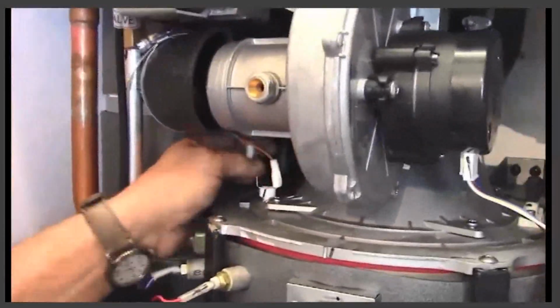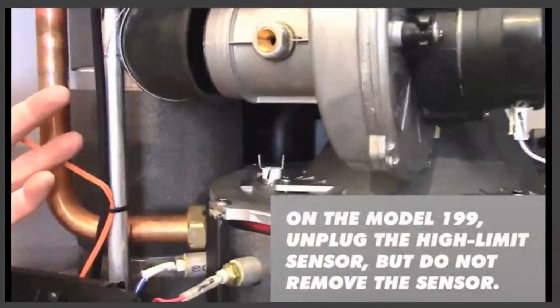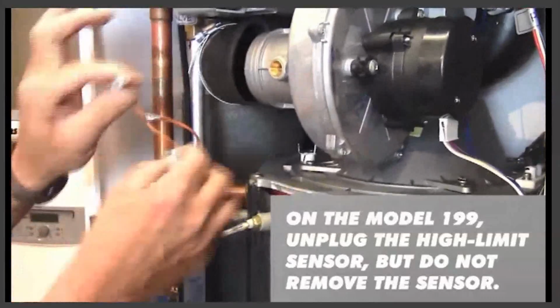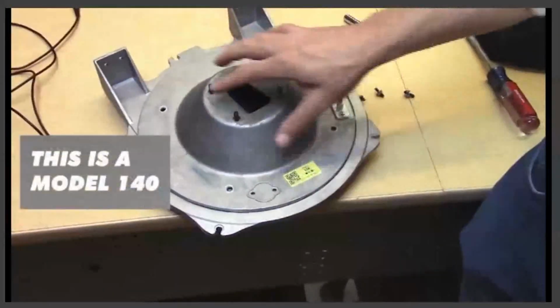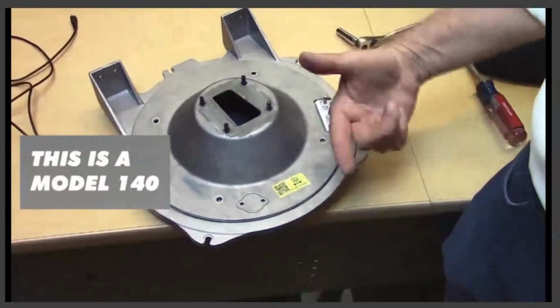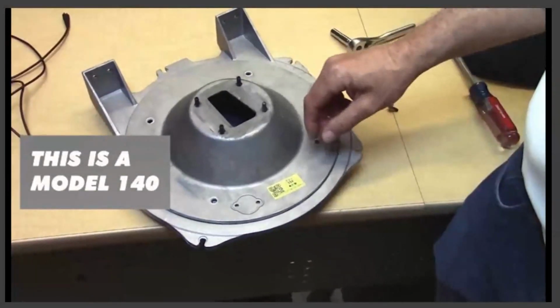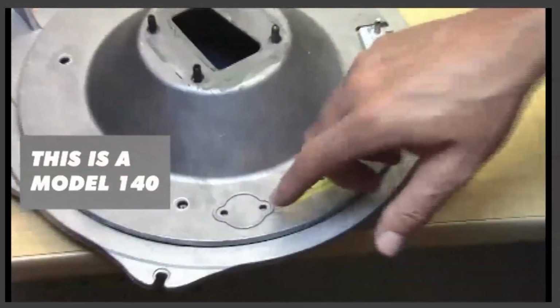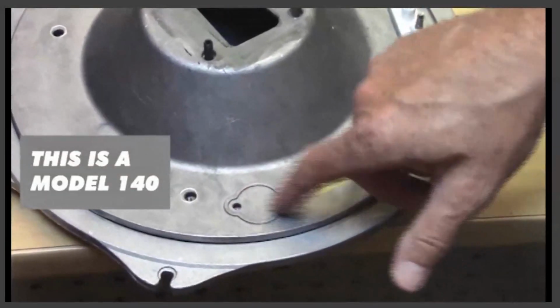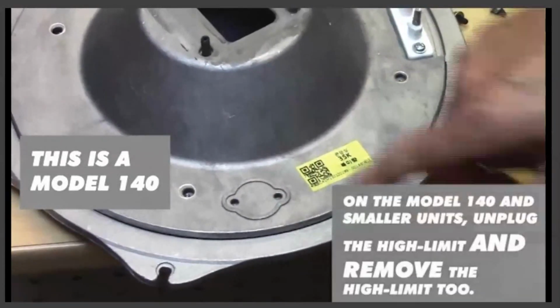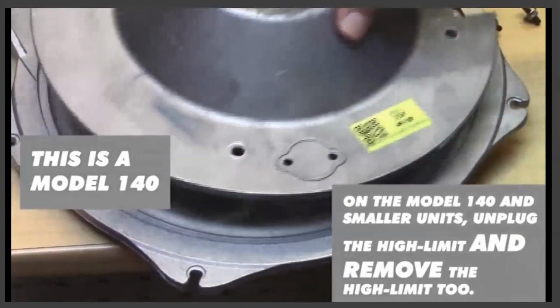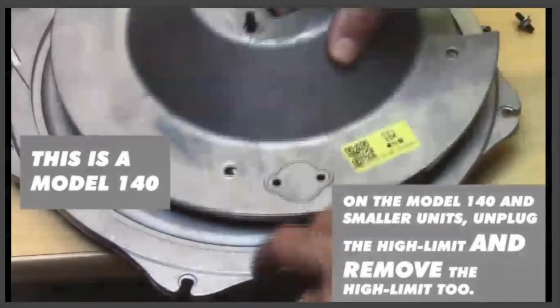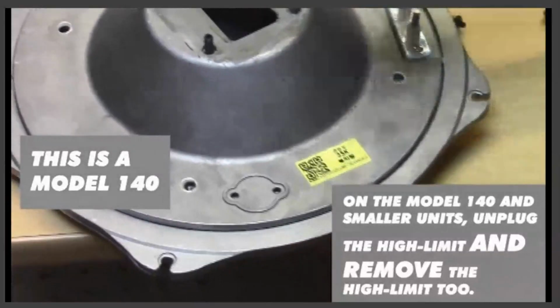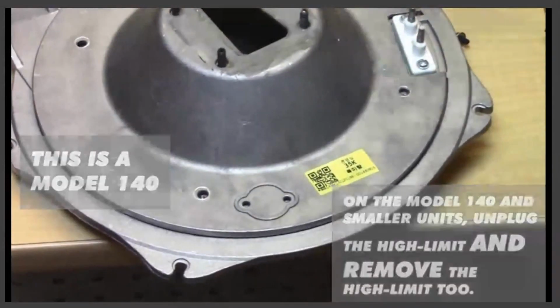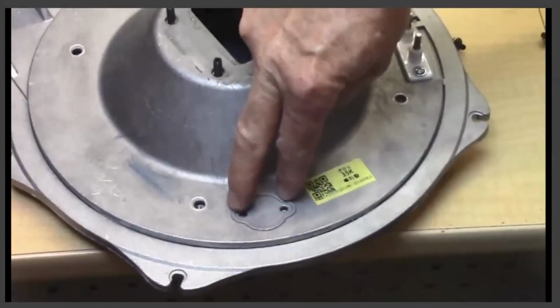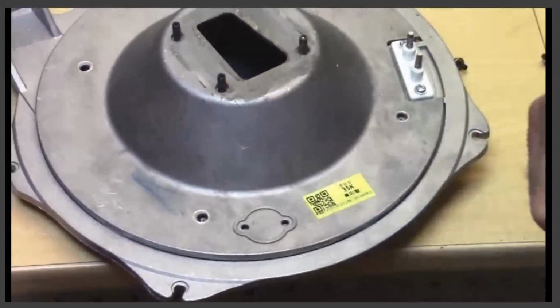Furthermore, removal of the high limit for the burner assembly, 2 wires. The orientation of these wires is unimportant. What we're showing here is the 140 burner plate that will come out. Currently, the boiler we're working on is a 199. However, there is a burner overheat sensor right here that does not have to come off. The 2 screws do not have to come out on the 199. On the smaller sizes, they do. Why? Because that comes right down through to the top plate. If you take out all of the nuts that hold the burner in position, on the smaller size you still also need to remove the 2 Phillips head screws for the burner limit.